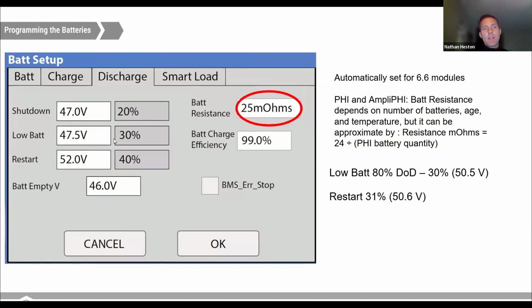Restart is for when the battery has hit a low voltage shutdown and the inverter has shut loads off. If you have solar on the system, it will allow the battery to charge back up to this value before starting discharge again. That way you're not having the inverter turn loads on and off when the loads are a little more than the solar can supply. Battery empty voltage should be set at 46, as I said earlier.